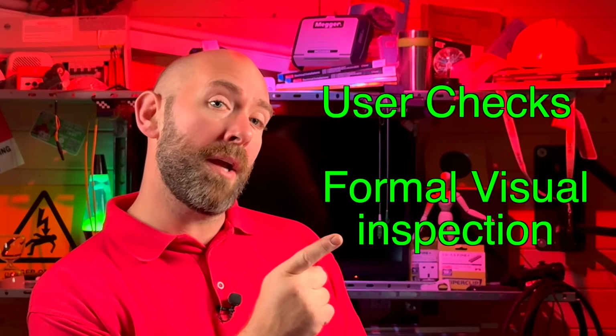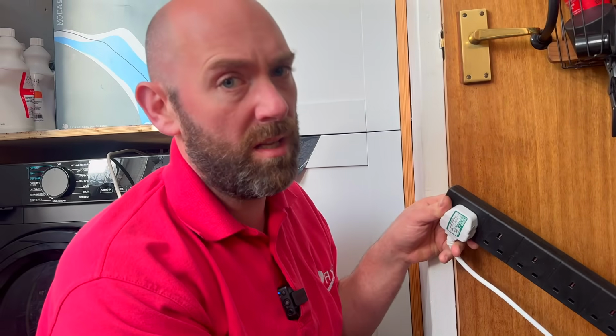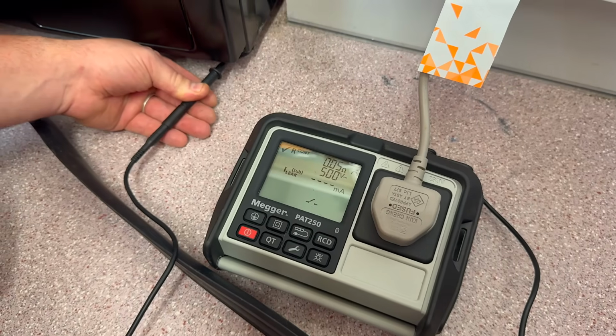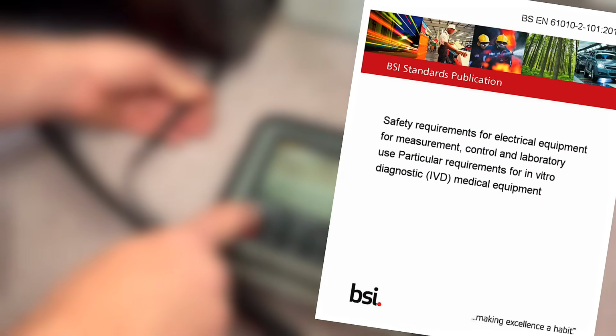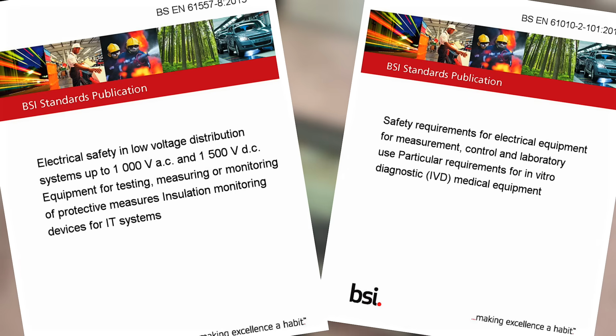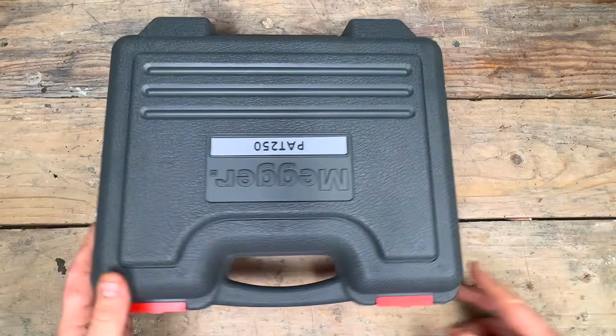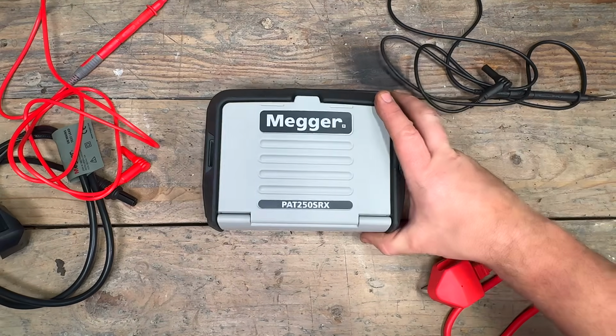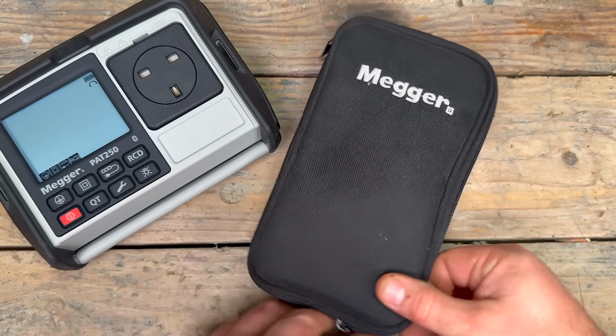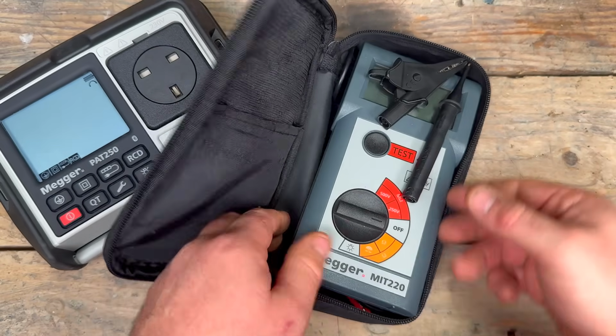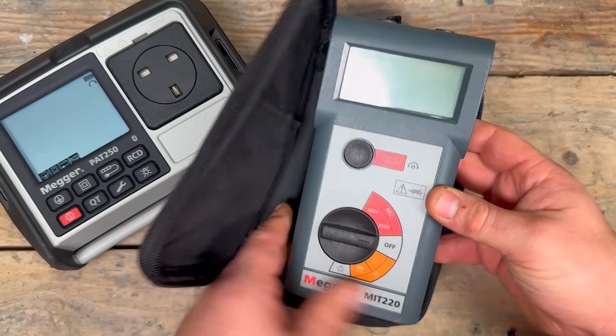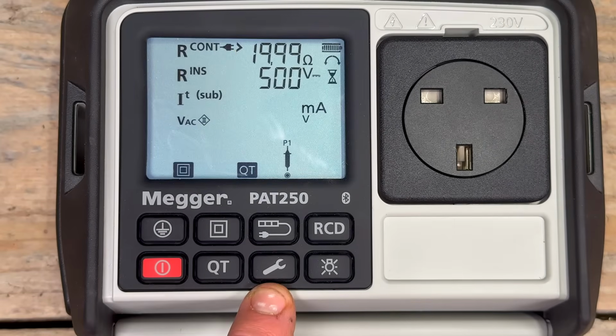Okay, so quick recap. We've done user checks and we've done formal visual inspection, and now it's time for the combined defined inspection and testing. So let's have a look at the piece of kit carrying out the test. A compliant tester must meet the requirements of BS-EN 61010 for safety and BS-EN 61557 for accuracy when testing protective measures. Modern dedicated PAT testers make this straightforward because they bring all the required functions together in one unit. But older or separate equipment can still be acceptable provided they meet the same standards for electrical safety and performance.